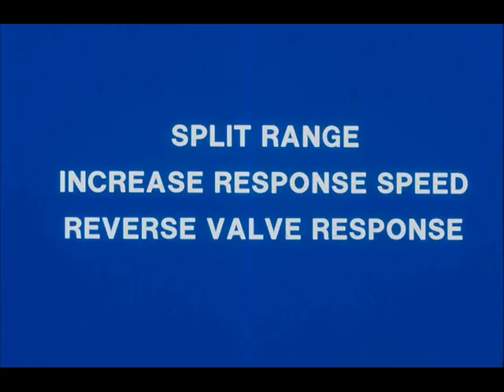It permits split ranging of valves. It also may be used to provide an increase in response speed, or to reverse the valve response to an instrument signal — that is, the instrument signal opens or closes the valve.